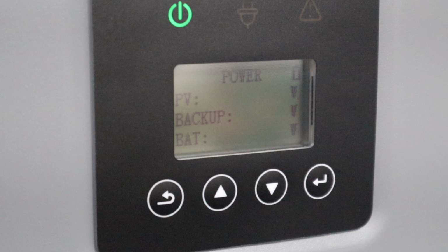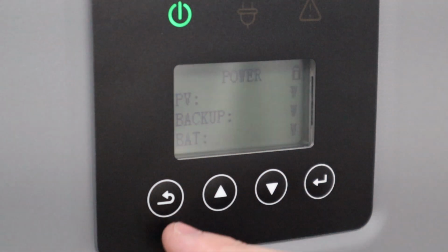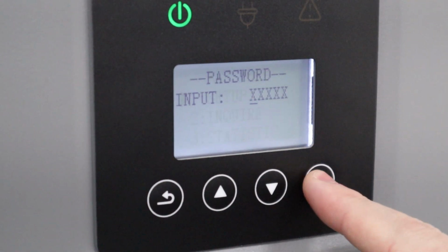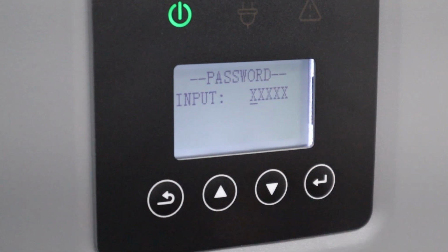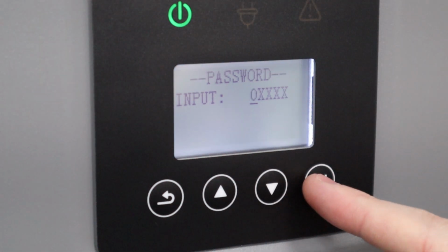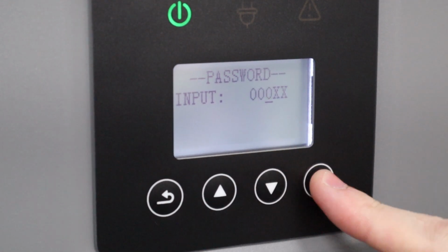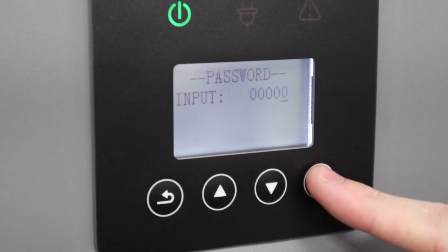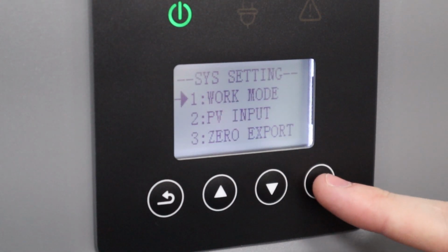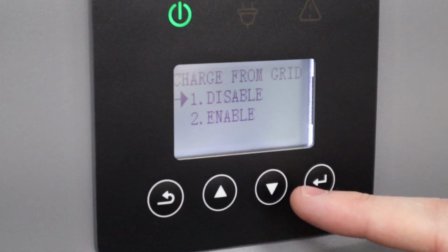Access the inverter operating menu using the 4 push buttons on the front of the inverter. They are the back button, page up, page down and return buttons. Press the back button until the user menu appears. Select Setup by pressing the return button. Enter the input password by using the page up or page down buttons and press return for each digit. The factory set passcode is 00000. Select System Setting, then Work Mode, then Self-Consume.